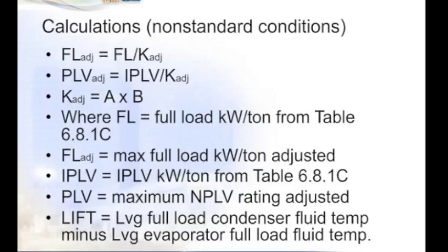We're going to go through the calculations and just identify the terms, and then go through a sample calculation a little bit later. But I think it's important to identify and discuss these so that we know what they're talking about in the formulas. So an adjusted full load value is the full load value from the table divided by the adjusted K value. Part load adjusted is still the integrated part load value divided by the adjusted K value. So what is the K value? Well, it's the constant that you calculate from terms A and B, which are calculated using the formulas.